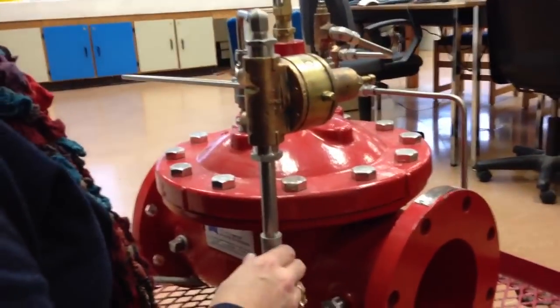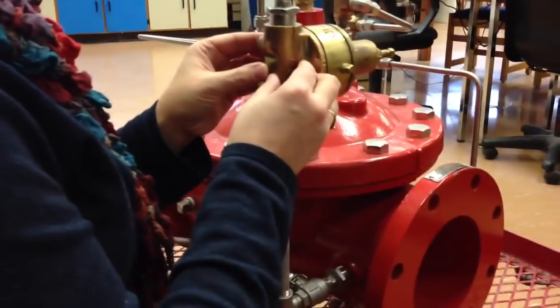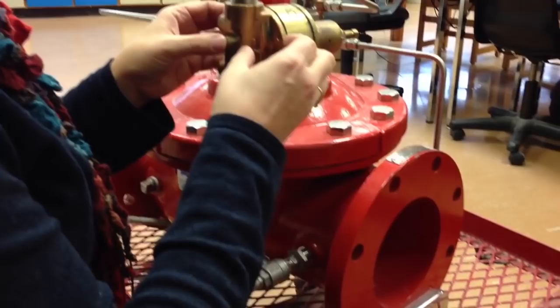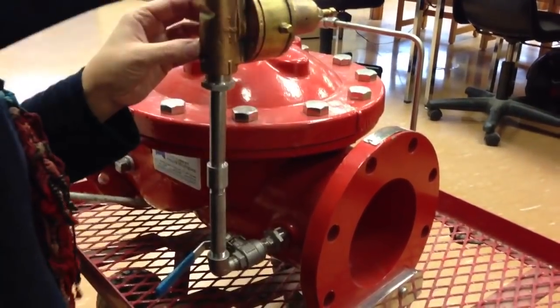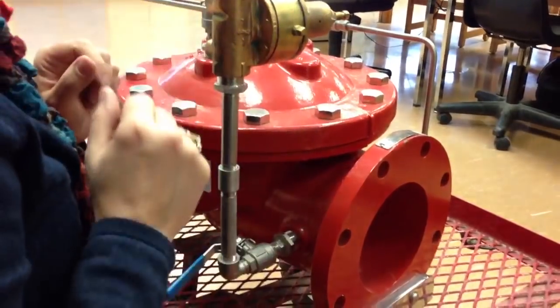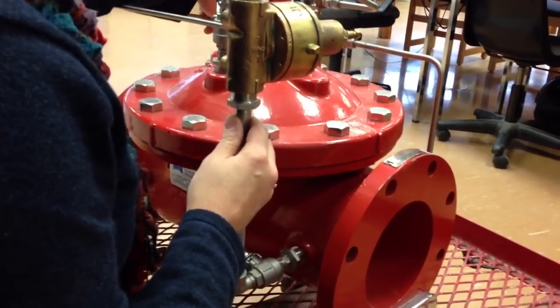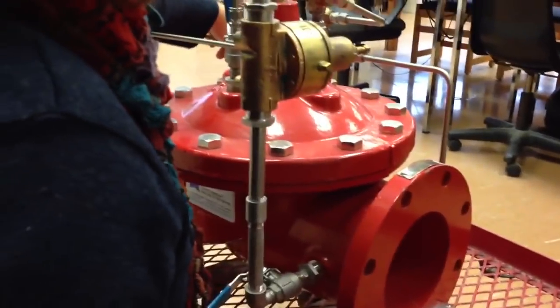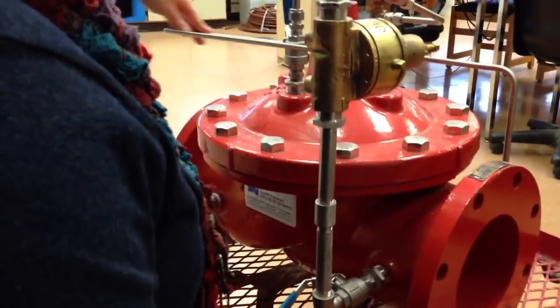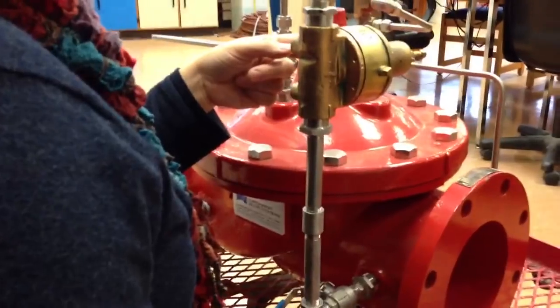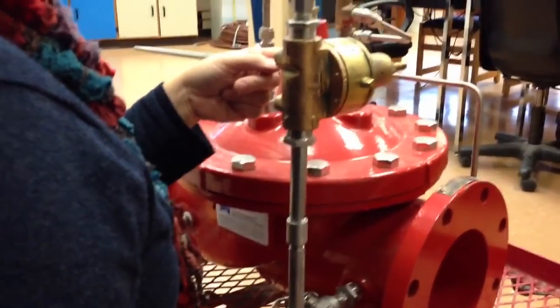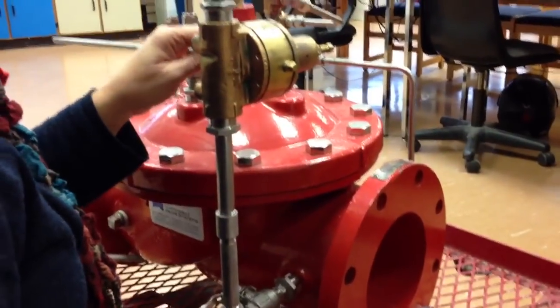let's go take a look at this guy here. What we've got happening here is this guy is a normally closed front seated valve. And it's got two completely separate chambers. It's got the valve body chamber, which is here, which allows water to pass through onto the top of the bonnet. And the other thing that it's got going on here is a sensing chamber that senses pressure off that. And that's sensing the downstream pressure. If it goes above 80, what's going to happen is this valve starts to close. Well, it starts to close it, but how does it start to close it?